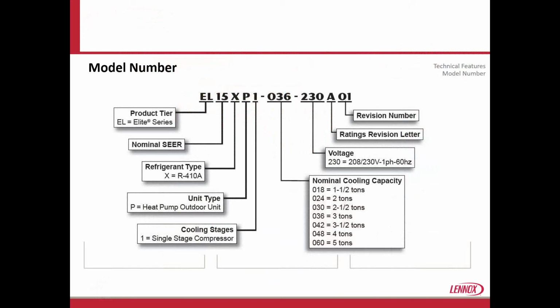And then the next digit will be how many stages that we have. In this particular scenario, we have one stage, and then we go into our nominal tons, ton and a half in this model, all the way up to 5 ton, and then 230 volts. Then we have some revision numbers on the very end. These are very important. I want to document that right now. As you guys start taking our model numbers and serial numbers and putting them into your computer system and documenting everything, make sure that you capture those revision numbers, because when the revision number changes, that means something inside the product changed. And when you get into Lennox Pros and start ordering parts, you can actually look up just that revision number only, so that you don't get multiple parts that might fit your unit. So that's very important to document.